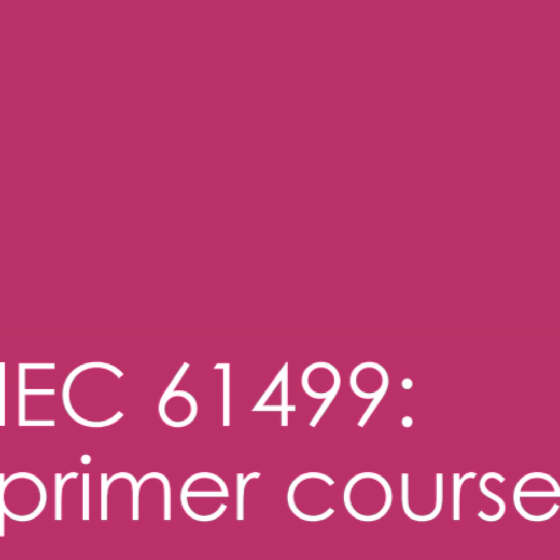And crucially, right after Q changes value either to true or false, that EO event output gets triggered. And EO isn't just like a notification. It's the signal that tells other connected function blocks, hey, something changed, maybe you need to do something now. Yeah. It propagates the change. I see. So it's not just saying, I've changed, it's actively triggering the next step, potentially. Does that mean the timing and reliability of that EO event are super important?